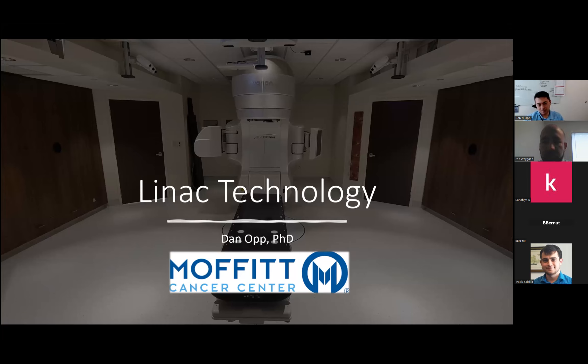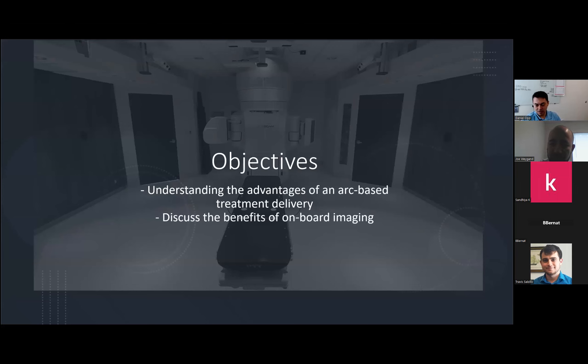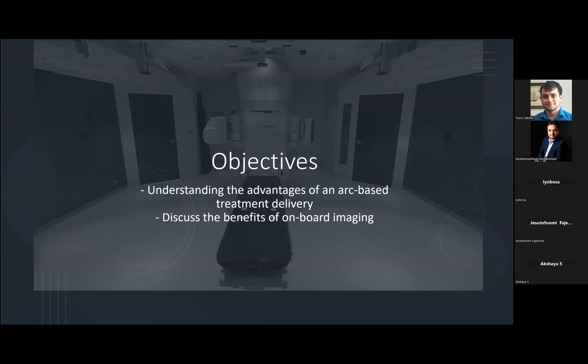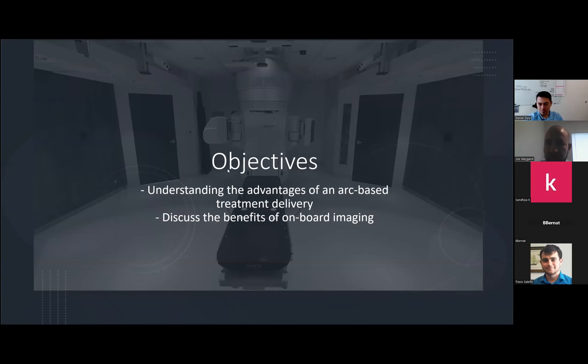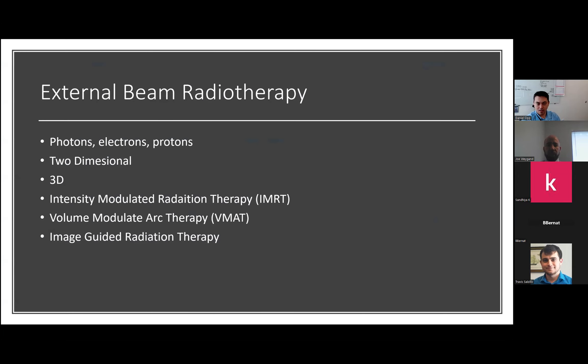Thanks Joe. My name is Dan, I'm a medical physicist at Moffitt Cancer Center. My topic today is linac technology, specifically focusing on VMAT and onboard imaging, which makes up probably 75 percent of our patient load. The objectives here are understanding the advantages of arc-based treatment delivery, or volume modulated arc therapy (VMAT), and discussing the benefits of onboard imaging. In the background is a picture of our second newest TrueBeam — on the left and right you can see a kV source and kV detector, which are the bread and butter of onboard imaging.